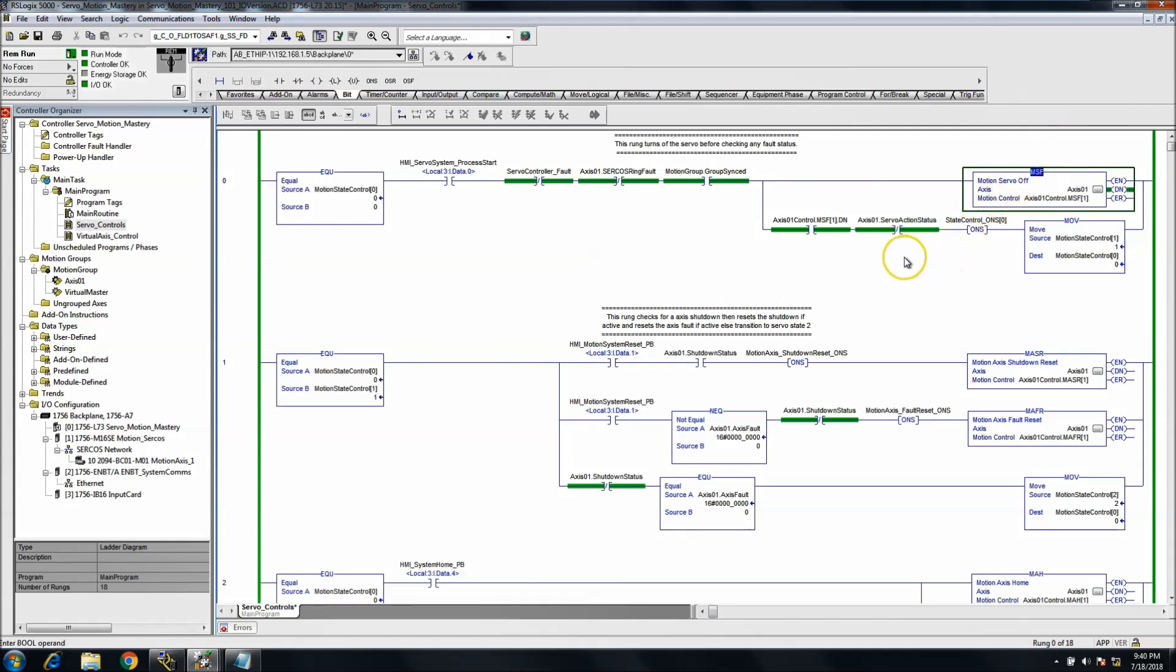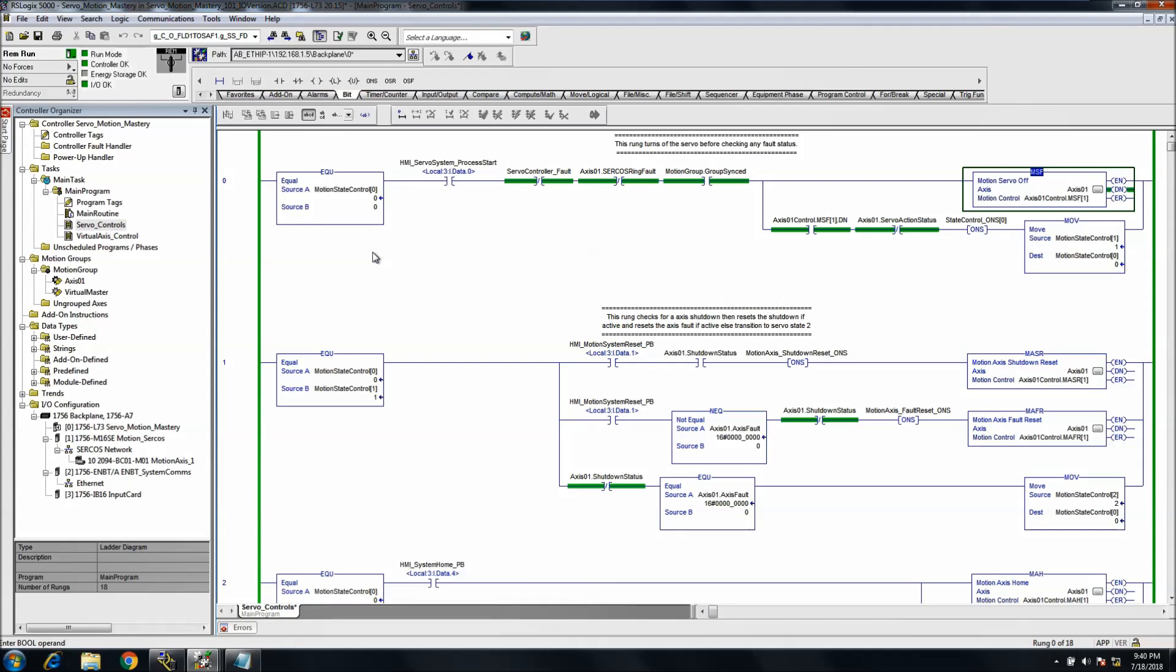I always choose to issue an OFF statement or an OFF instruction before I do anything else because you don't know for sure what state the controller is in at any given time. You could have lost communications, you could have had some weird anomaly happen. You don't know for a fact that the servo controller hasn't been told to run already or hasn't been told to cut on, or could possibly be in an ON state for some other control reason that you weren't aware of.